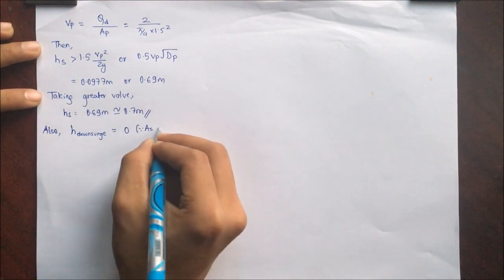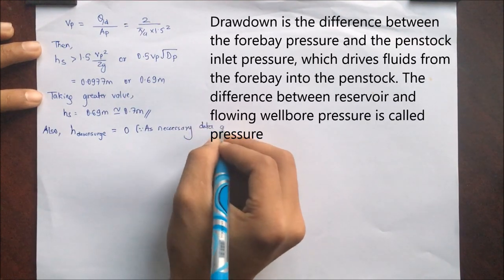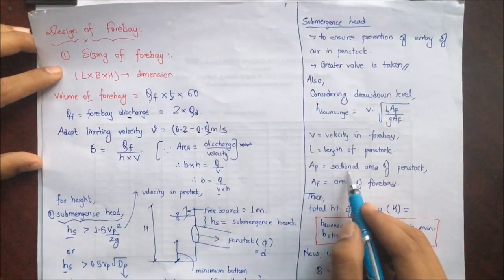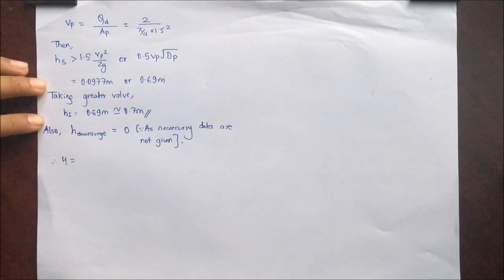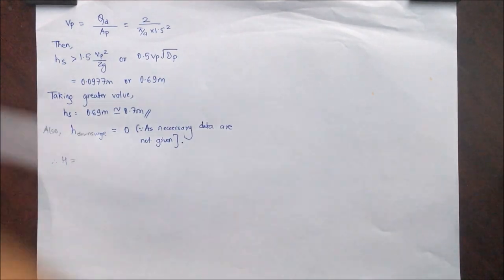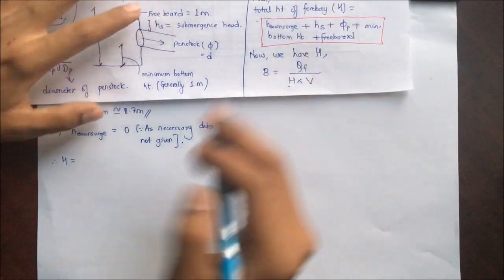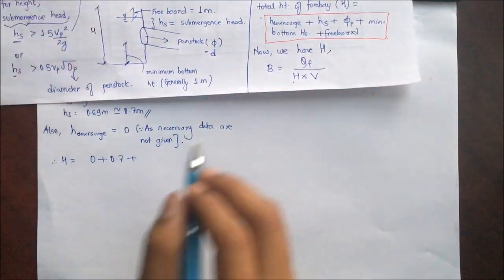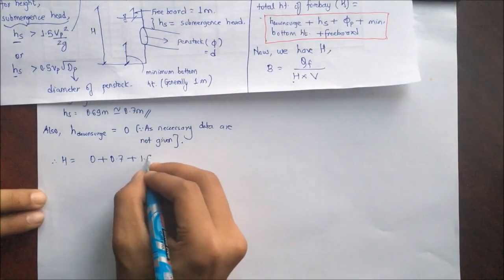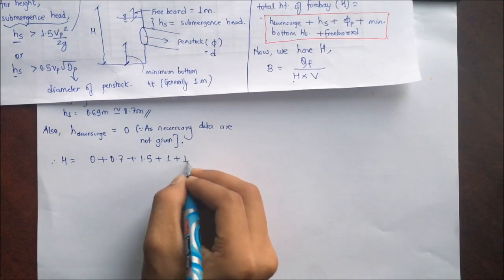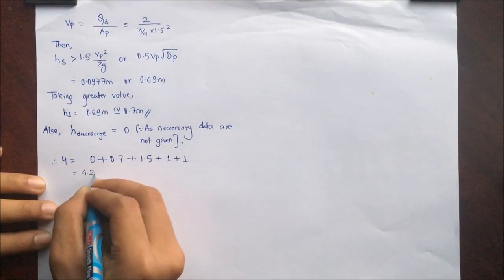H_drawdown is taken as 0 since necessary data are not given. Values like Af and Ap were not provided, so H_drawdown = 0. Now substituting values for total height H: H_drawdown = 0, Hs = 0.7 m, diameter = 1.5 m, freeboard = 1 m, and minimum bottom height = 1 m. This gives total height H = 4.2 meter.